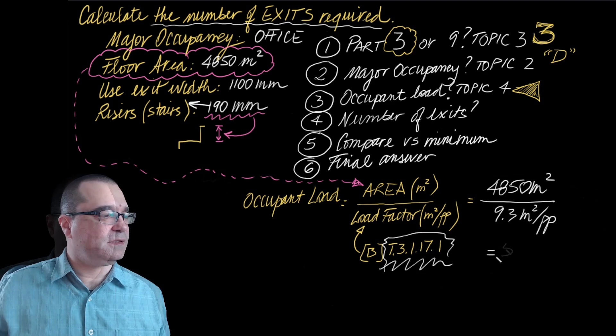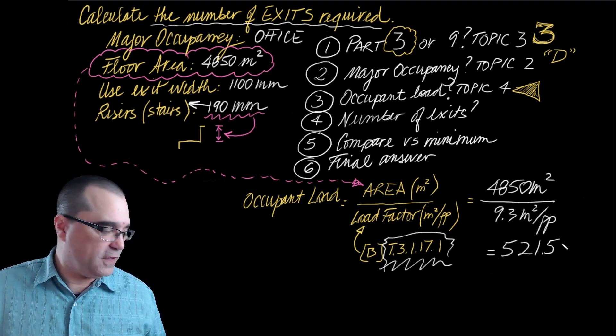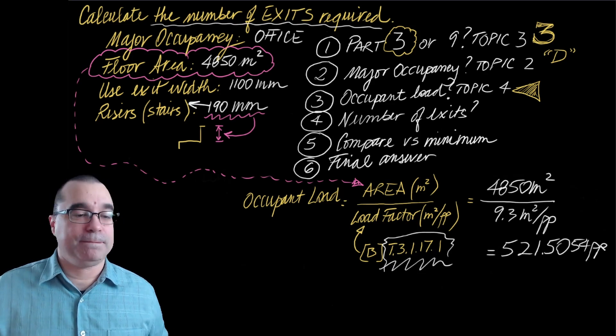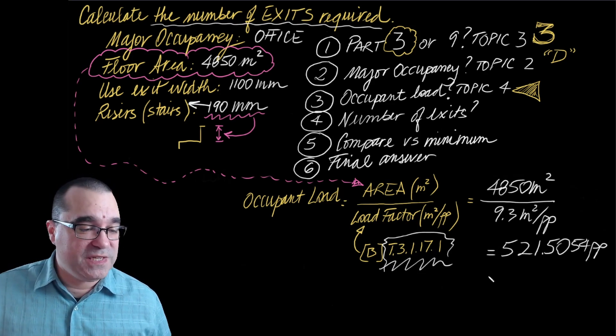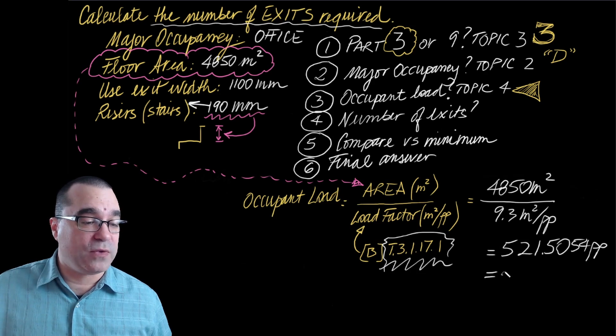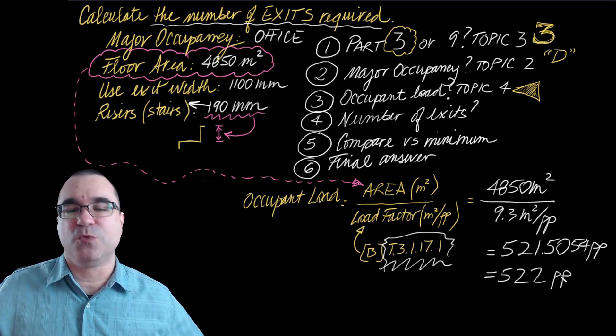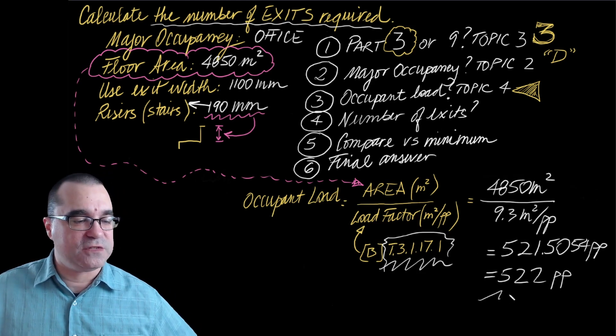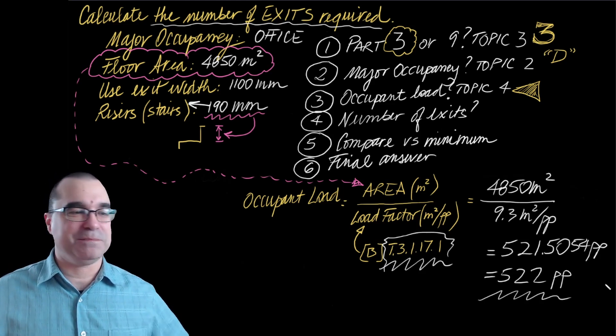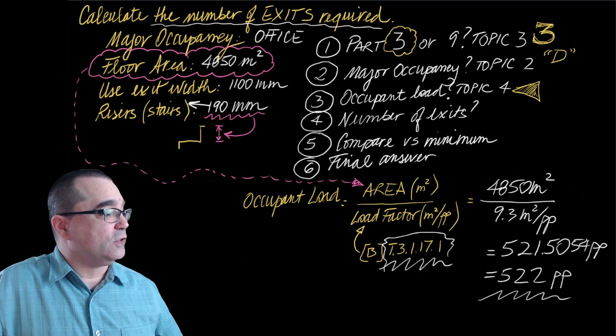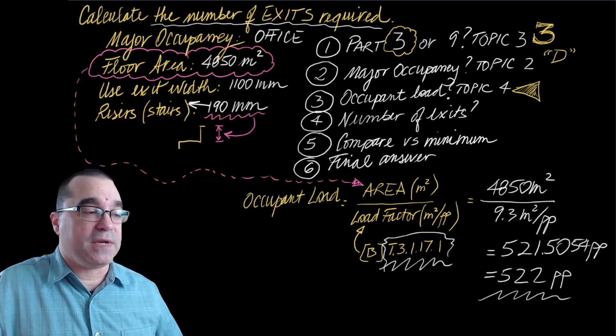So when I calculate that number, I get 521.5054, and so on. Because human beings are a whole number, we always round up because this number means more than 521. And the smallest whole number that is more than 521 is 522. Awesome. We now have, according to step number three, the occupant load for this space. Let's move on to step number four.